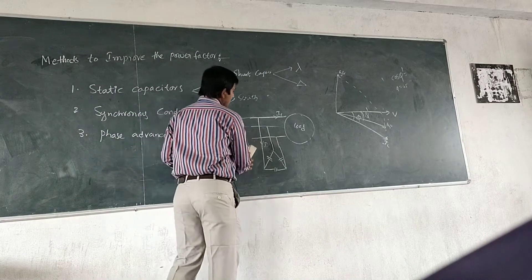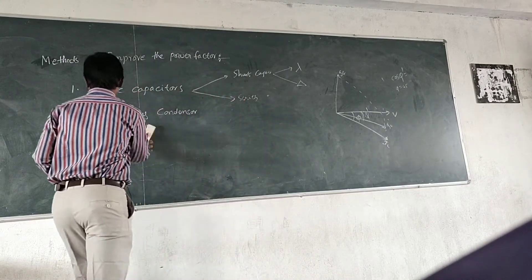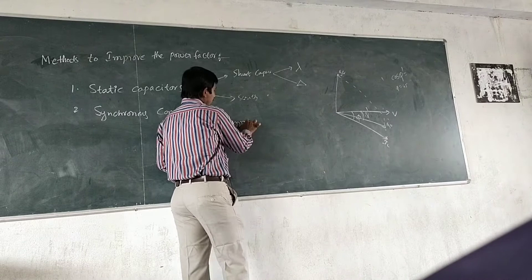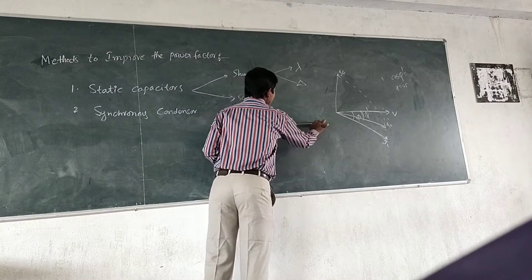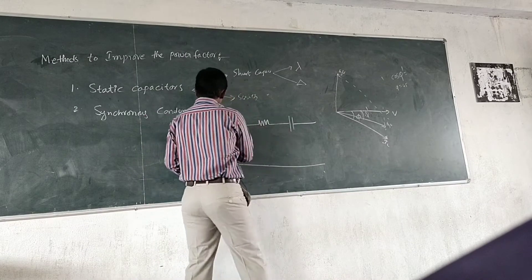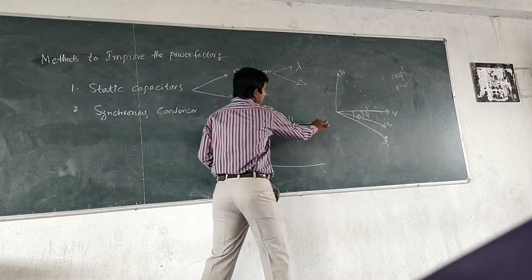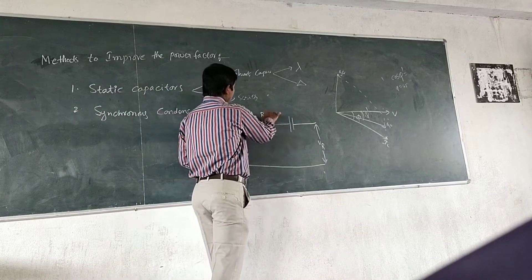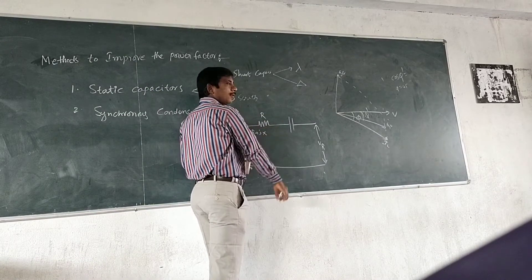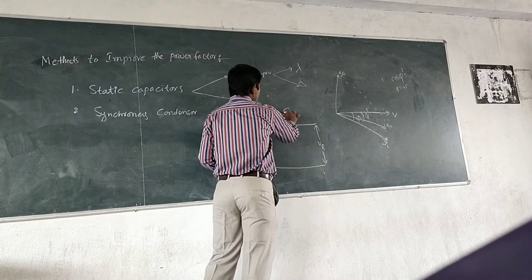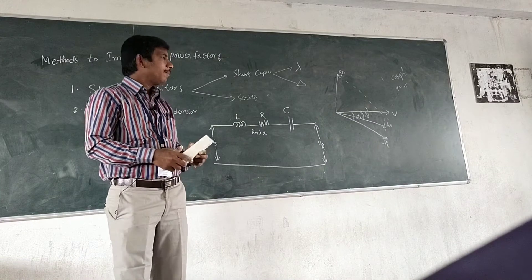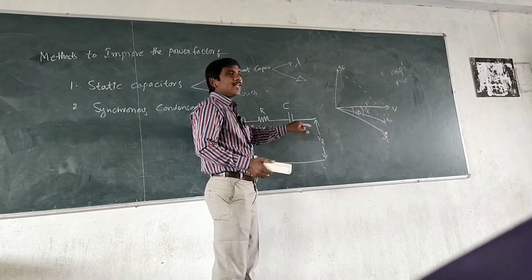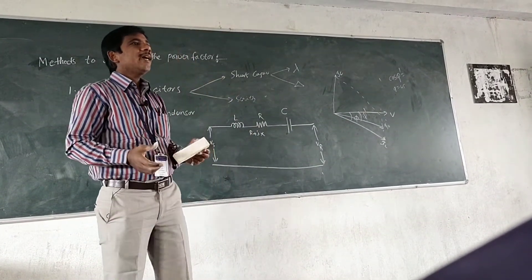Next, the series capacitors will be connected in series with the transmission line. This is the sending-end voltage and the receiving-end voltage. The impedance of the line is there, and then there is a series capacitor. Series capacitor improves the voltage level by injecting reactive power. It improves the voltage level of the system. Whereas shunt capacitors improve the power factor by injecting reactive power.